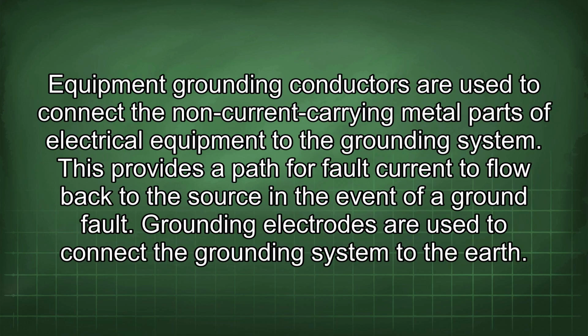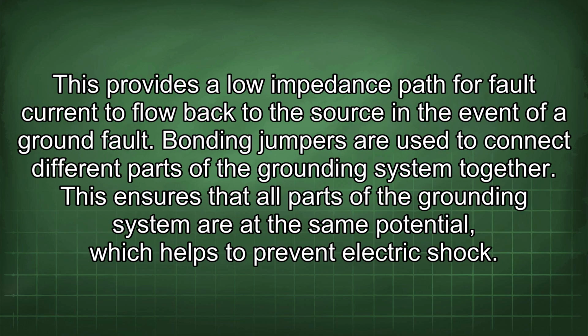Equipment grounding conductors are used to connect the non-current carrying metal parts of electrical equipment to the grounding system. This provides a path for fault current to flow back to the source in the event of a ground fault. Grounding electrodes are used to connect the grounding system to the earth. This provides a low impedance path for fault current to flow back to the source in the event of a ground fault. Bonding jumpers are used to connect different parts of the grounding system together. This ensures that all parts of the grounding system are at the same potential, which helps to prevent electric shock.